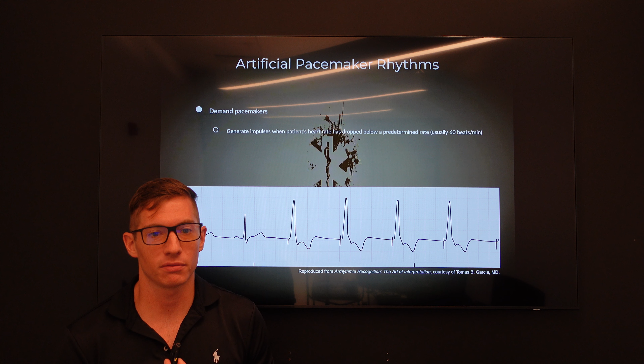Sometimes there are implanted pacemaker malfunctions, and the types of pacemaker failure include the following. It could be failure to capture. Pacemaker spikes may be visible, but they will not be followed by a QRS complex. It could be dislodged wiring connecting the patient's heart to the pacemaker, battery depletion, or ventricular perforation. Failure to pace is indicated on the ECG by absence of the pacemaker spikes at an expected time. So the pulse generator could have failure, broken lead wire or dislodged lead, disconnected wire or cable, or battery depletion.